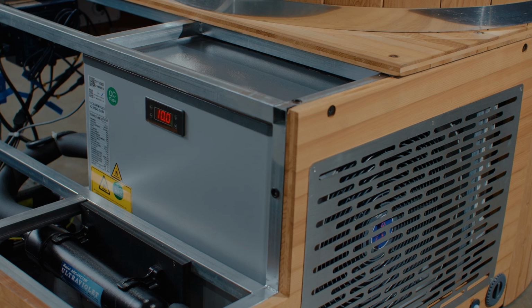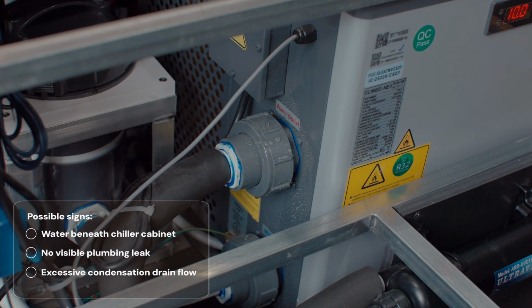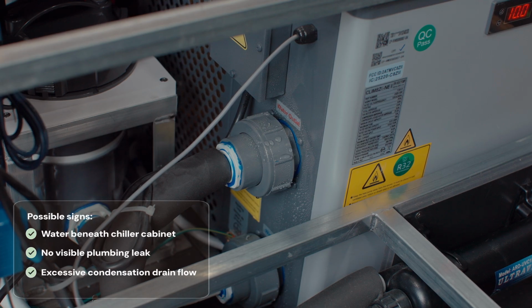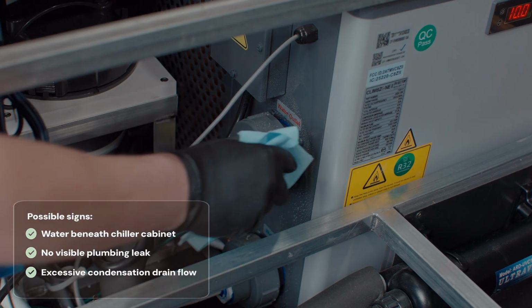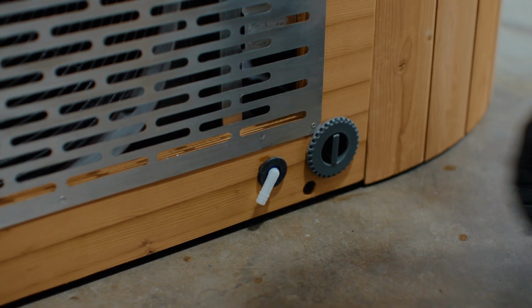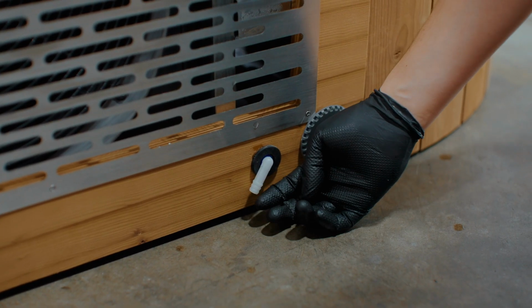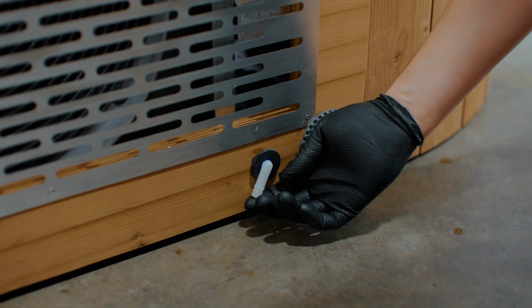If no external plumbing leaks are found, inspect the Balboa Chiller assembly itself. Internal chiller leaks may present as water dripping directly from inside the chiller cabinet or pooling beneath the unit without visible leakage from hose connections or unions. Also inspect the condensation drain line, the small white tube connected to the chiller, to confirm it has not become loose or disconnected.